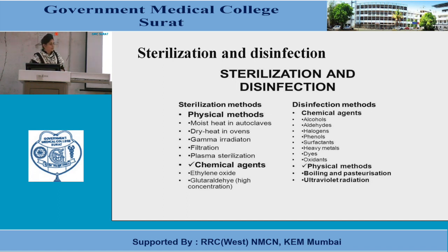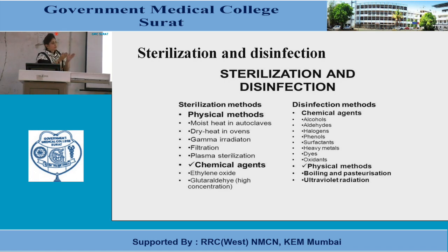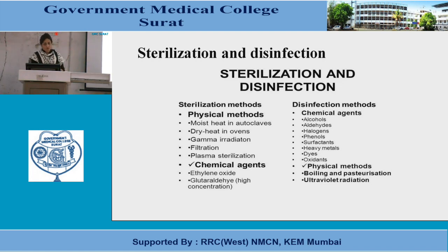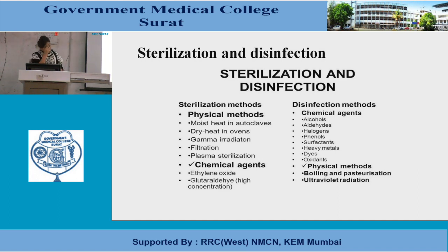It is absolutely important to remember there is a required duration for disinfection. In sterilization, autoclaving is at a particular temperature, 15 pounds per square inch pressure for 30 minutes; flash sterilization for five minutes. Duration is critical — you cannot dip instruments in the disinfectant for five minutes and remove them expecting it to work. For disinfection you need 20 minutes. If you want to use the chemical for sterilization to kill spores also, you must leave the instruments for six hours.